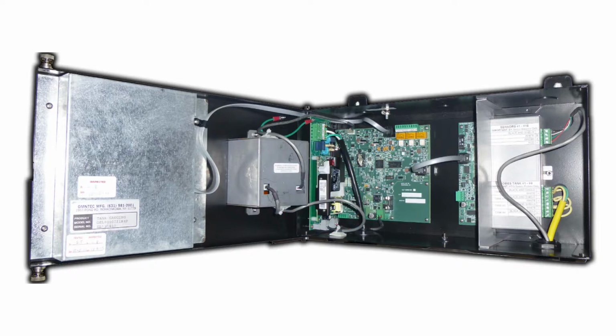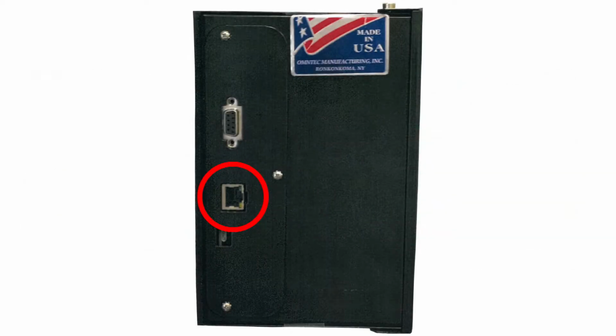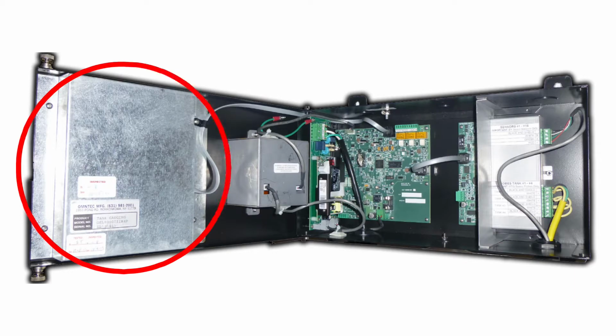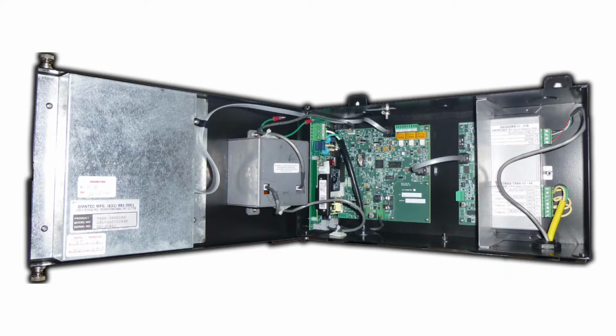On the back left side is mounted the main control unit, or MCU board. A red RS485 communications board, optional on the Proteus K, can be mounted on the MCU. On the back right side is mounted one of 2 different probe and sensor interface boards, which are explained later. The interface board will have a metal barrier to separate the intrinsic and non-intrinsic side of the interface board. The TCP/IP, RJ45, and serial RS232, DB9 communication ports are located on the left side of the controller. Again, when the door is closed, the metal plate of the display and the metal barrier over the interface board produces an intrinsically safe compartment for the probe and sensor inputs.